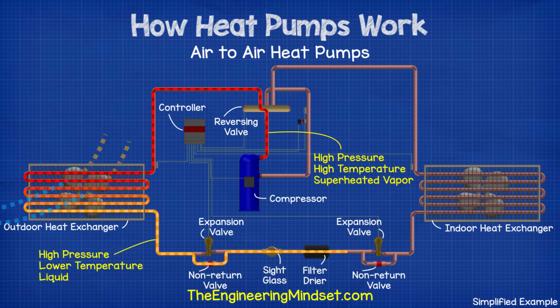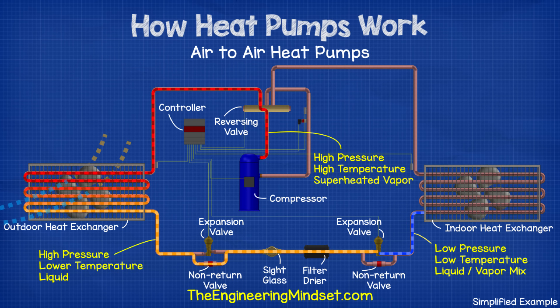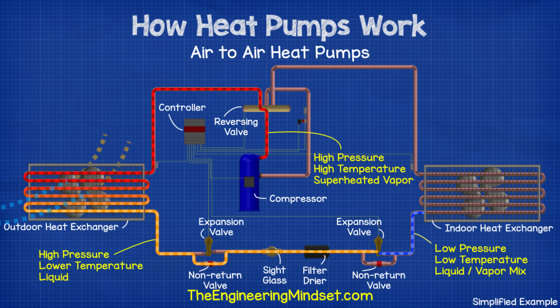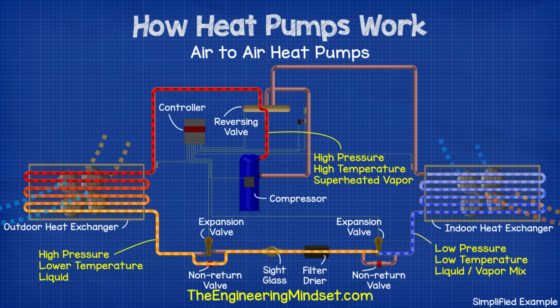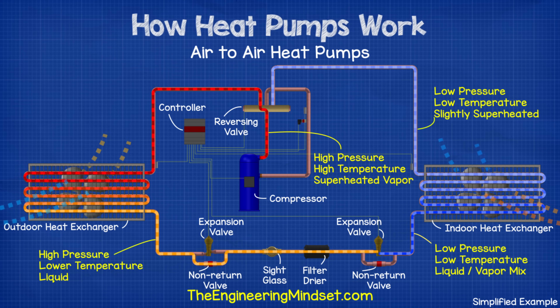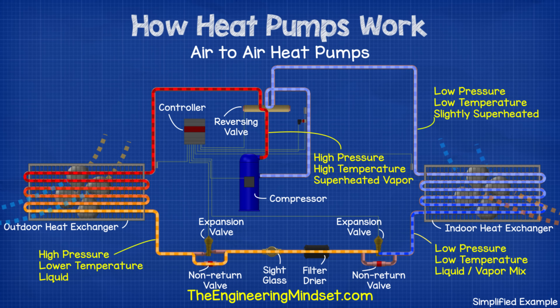It then passes through the sight glass and the bidirectional filter dryer. The next non-return valve is then closed, so the refrigerant passes through the expansion valve. As it passes through the expansion valve, the refrigerant changes to a part liquid, part vapor mixture, which causes it to drop in pressure and temperature. It then flows into the indoor heat exchanger, where a fan blows the warm indoor air over the coil. This causes heat to transfer from the air into the refrigerant, so the refrigerant boils and takes this heat away. The refrigerant leaves the indoor unit as a low pressure, low temperature, slightly superheated state, and flows into the reversing valve, which diverts it back to the compressor to repeat the cycle.